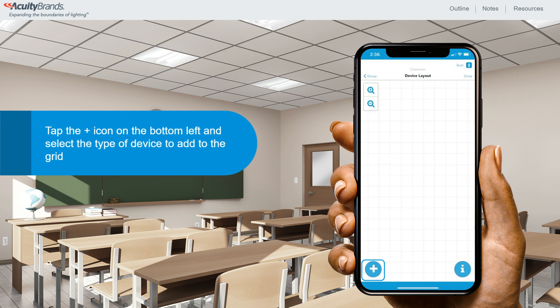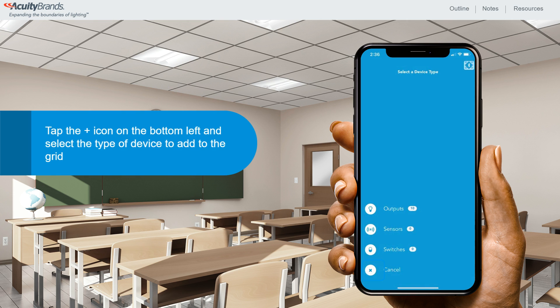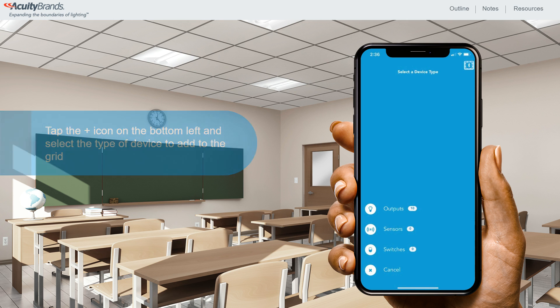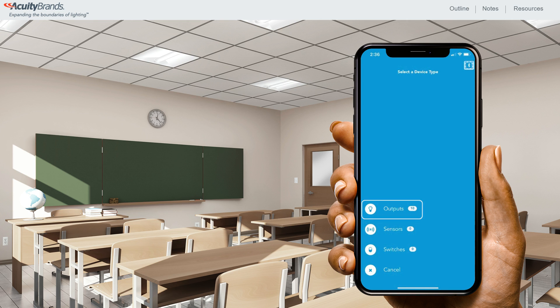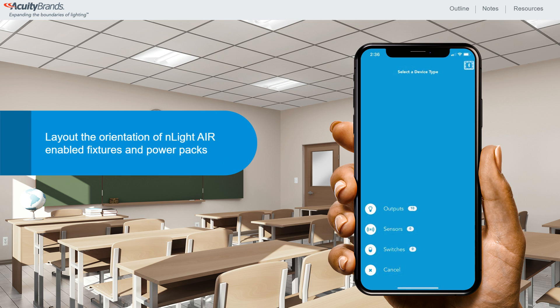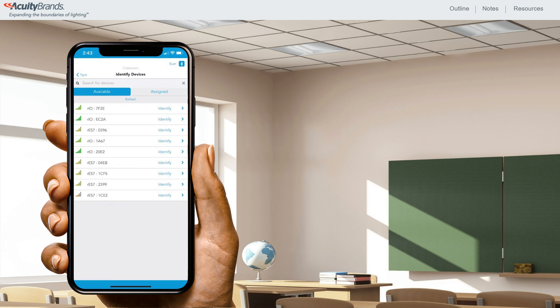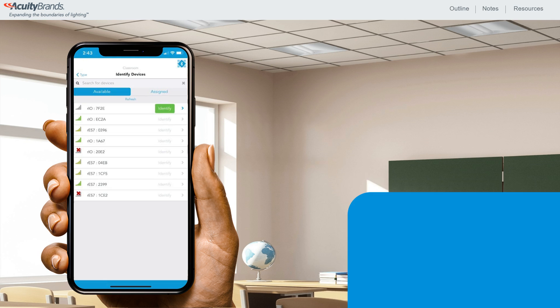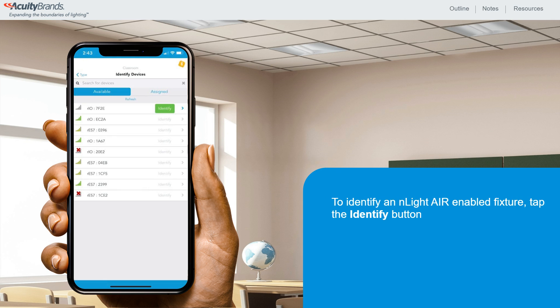Tap the plus icon on the bottom left and select the type of device to add to the grid. The first device in the group to be added to the grid cannot be a battery powered device, so tap on the icon that looks like a light bulb for outputs. Then you'll enter a mode that allows you to layout the orientation of the nLight AIR enabled fixtures or any power packs. Once you've selected the type of device to discover, the Identify Devices screen will show you a list of nLight AIR devices sorted by signal strength. To identify an nLight AIR enabled fixture, tap its Identify button, then look at the fixtures.